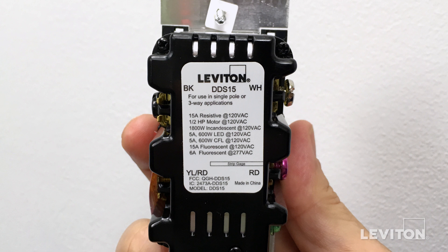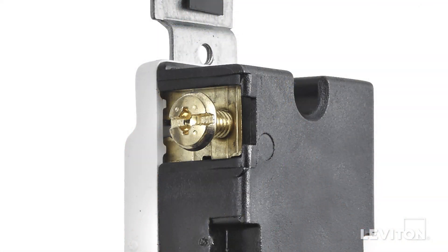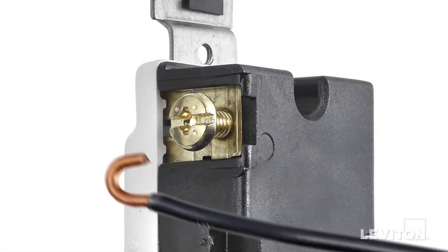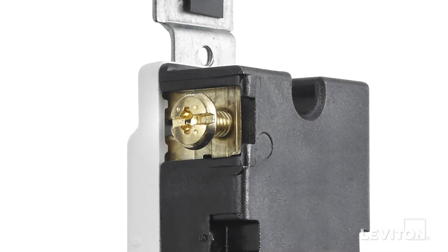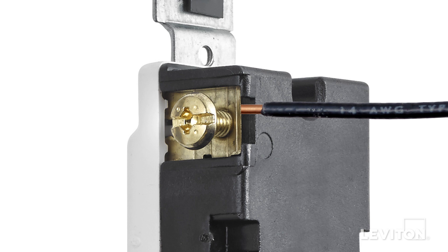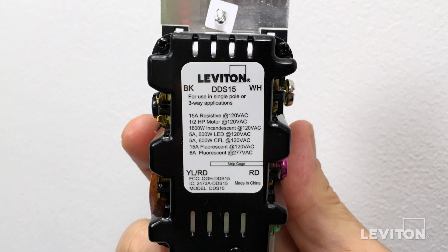This device is equipped with terminal screws and can be wired two ways: side wire or back wire. Side wiring is done by wrapping the conductor around the terminal screw. Back wiring is done by inserting the conductor under the clamp of the terminal screw. For this installation, we will be using back wiring.